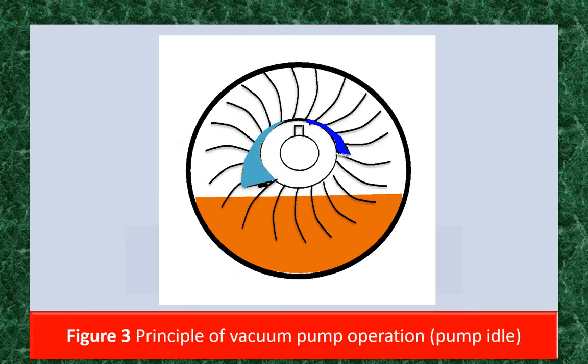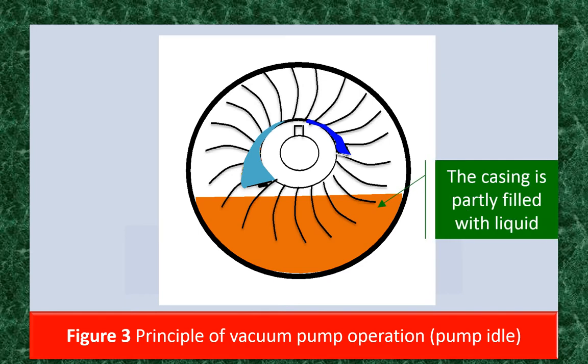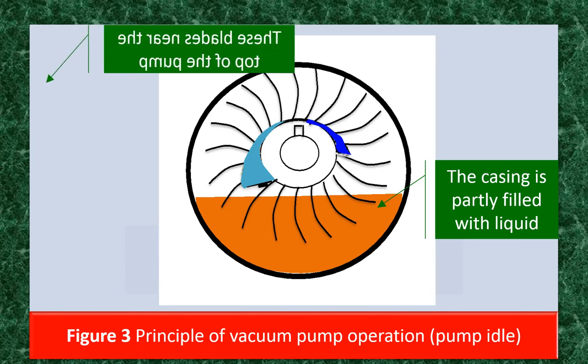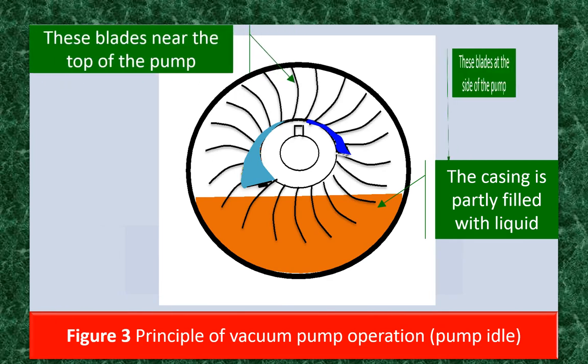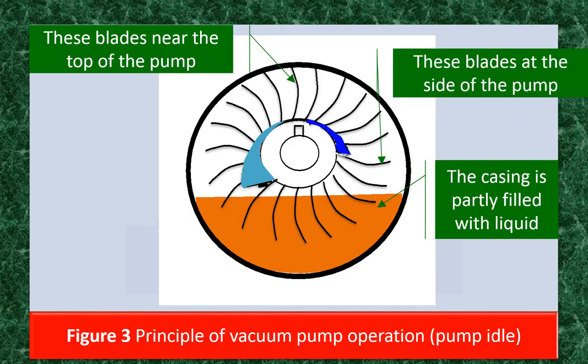In the figure shown, the pump is in idle condition — that is, it is not working. The pump is partly filled with sealing liquid shown in brown color. Sealing liquid fills the casing roughly 50% and remains at the bottom. The blades near the top of the pump are closer to the outside wall than at the side of the pump. The bottom ends of the impeller blades are immersed in the sealing liquid.